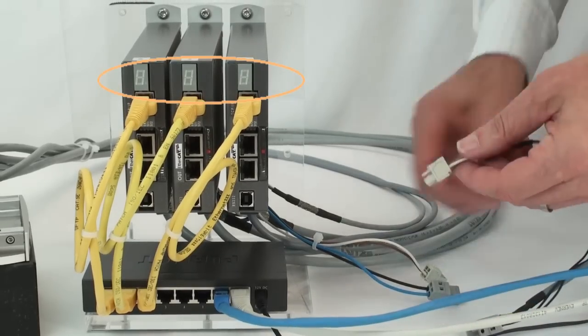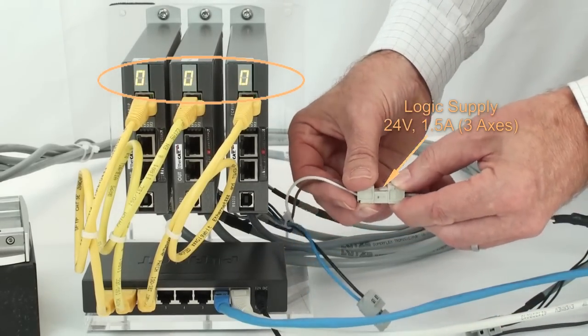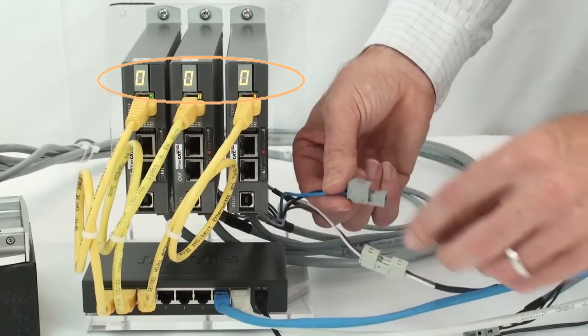The logic supply is always 24V DC. The power supply voltage depends on the LINAX type and the requested speed. If you have a LXC compact linear motor axis with only 10 N nominal force, then a 24V power supply with 5 A is sufficient. If you have a 24V power supply, you could use the same supply source as for the logic supply. In that case, you would need only one supply device.